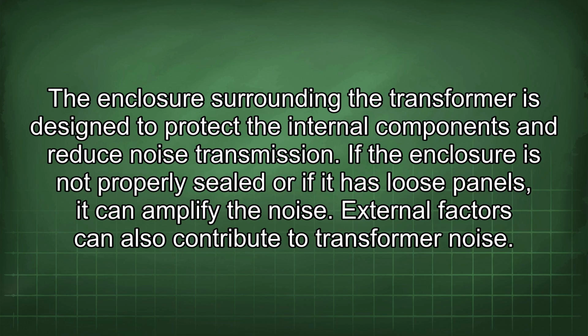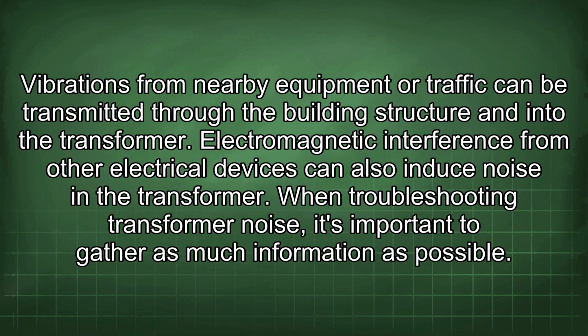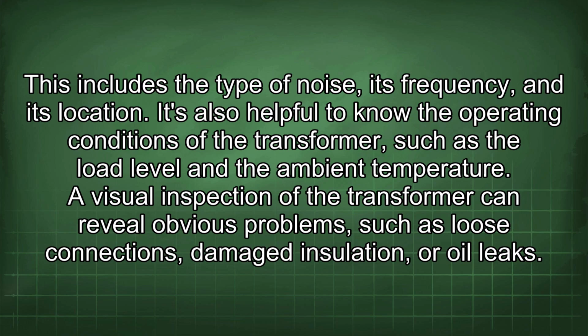External factors can also contribute to transformer noise. Vibrations from nearby equipment or traffic can be transmitted through the building structure and into the transformer. Electromagnetic interference from other electrical devices can also induce noise in the transformer. When troubleshooting transformer noise, it's important to gather as much information as possible. This includes the type of noise, its frequency, and its location. It's also helpful to know the operating conditions of the transformer, such as the load level and the ambient temperature.